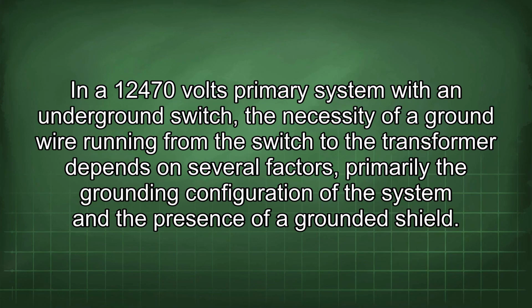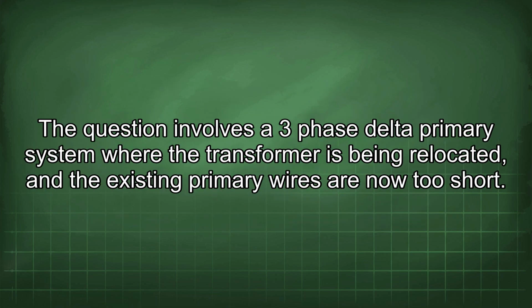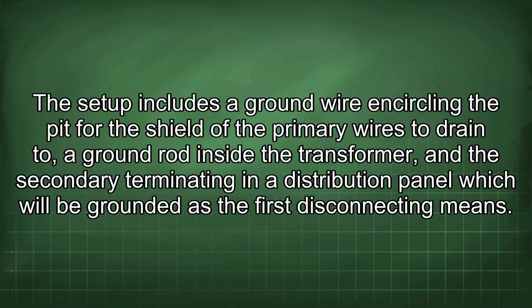In a 12,470 volts primary system with an underground switch, the necessity of a ground wire running from the switch to the transformer depends on several factors, primarily the grounding configuration of the system and the presence of a grounded shield. The question involves a three-phase delta primary system where the transformer is being relocated, and the existing primary wires are now too short. The setup includes a ground wire encircling the pit for the shield of the primary wires to drain to, a ground rod inside the transformer, and the secondary terminating in a distribution panel which will be grounded as the first disconnecting means.